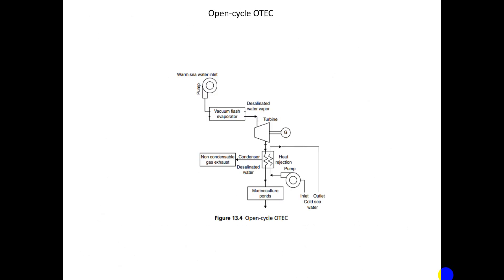Looking at the diagram, this is the open loop OTEC: the input is warm sea water which enters through a pump going to the flash vacuum evaporator, producing desalinated water vapor. It then moves to the turbine to drive the turbine blades and generate electricity. From there it moves to the heat condenser, after which cold sea water is discharged outside. From the condenser, non-condensable gases are exhausted and the desalinated water is directed to marine culture ponds. This is an open cycle — not a closed loop — and we call it open cycle OTEC.